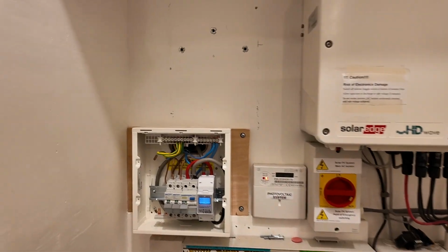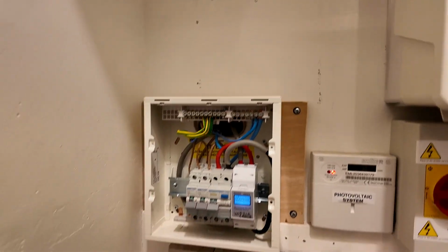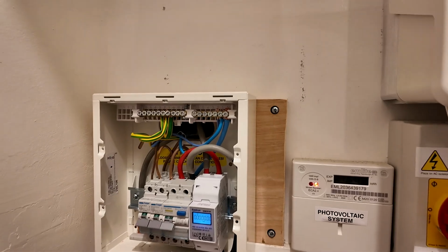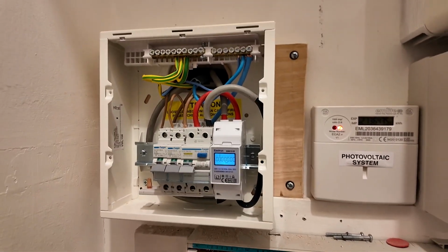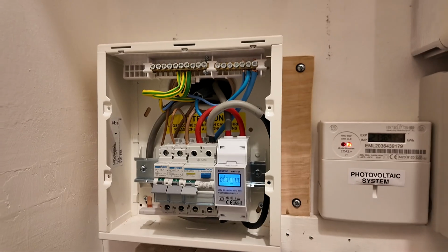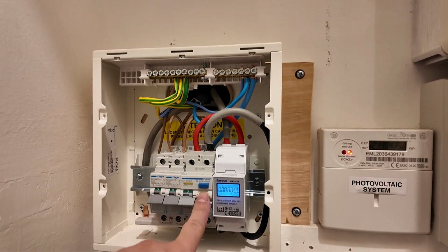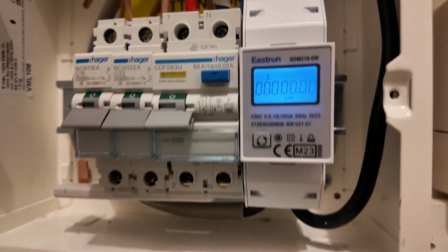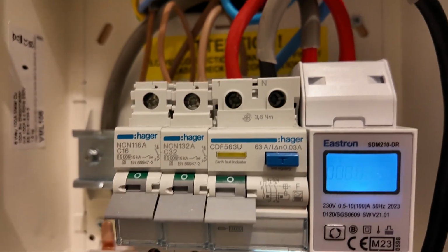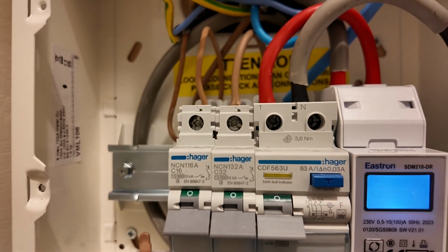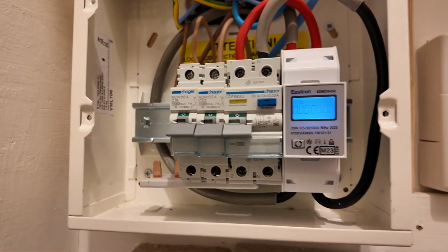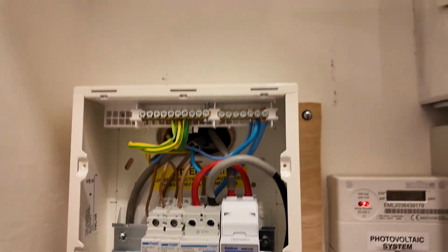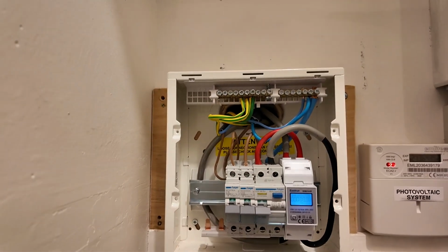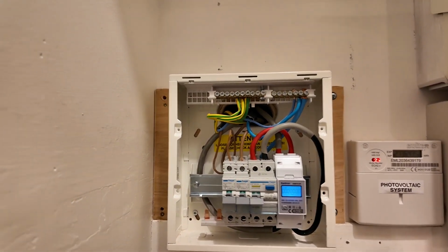So here's the electrics. It's a new board which is coming in. There's an electricity meter just for the heat pump. A unique feature about heat pumps, they've got a type F RCD right there. So we have got 2 breakers here. I think there's going to be another breaker somewhere else. I'm not too sure where, but 2 breakers. I think one for the indoor unit, one for the outdoor unit. And then there's 2 more spares for future expansion.